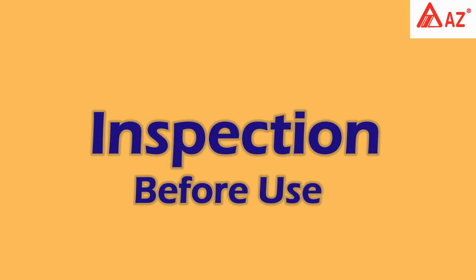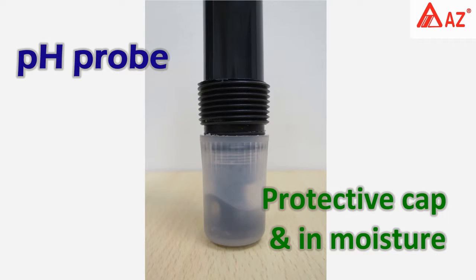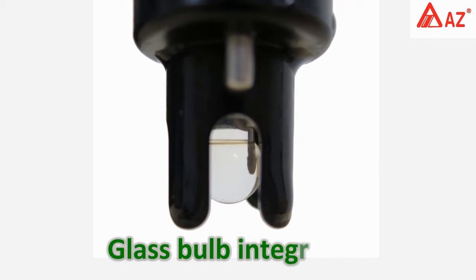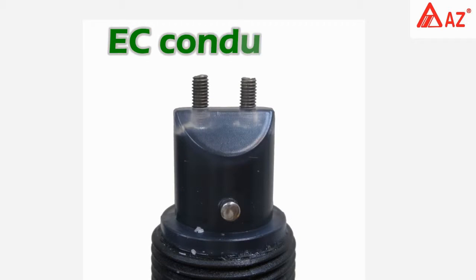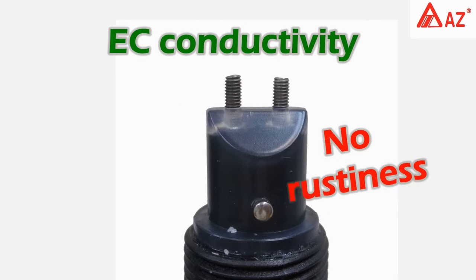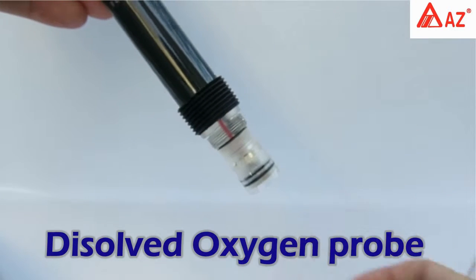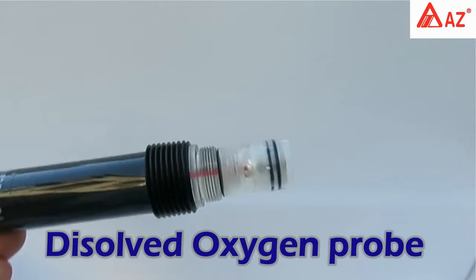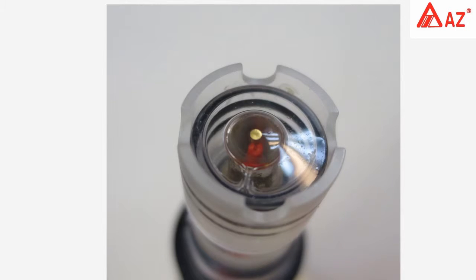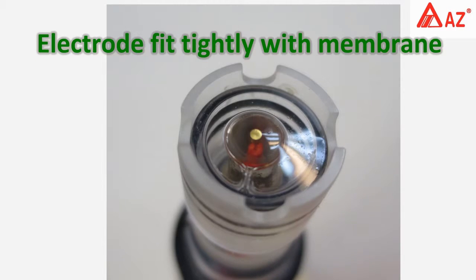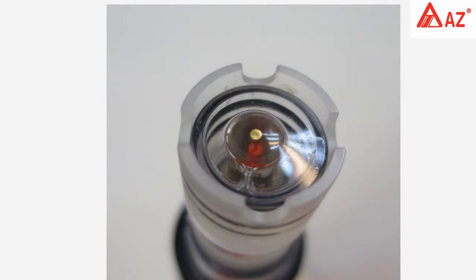Inspection before use. Keep the pH probe in its protective cap and in moisture. The glass bulb should be intact. There should be no rustiness on the EC conductivity electrode. For the dissolved oxygen probe, remove the anti-collision hood. Nothing should be broken, and the electrode should fit tightly with the membrane set.